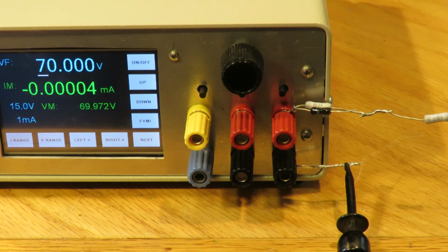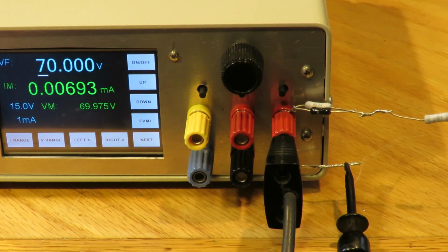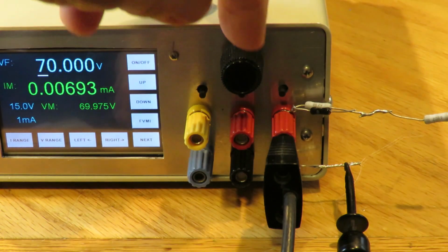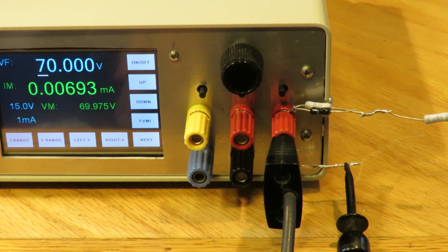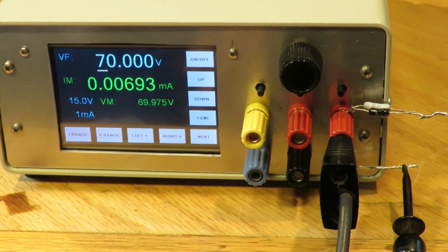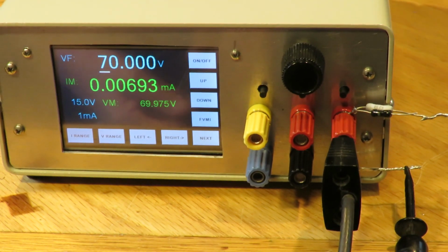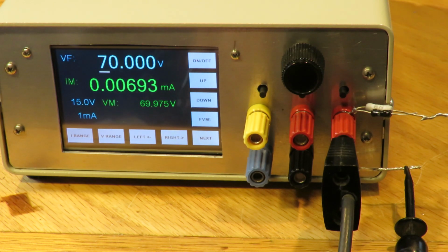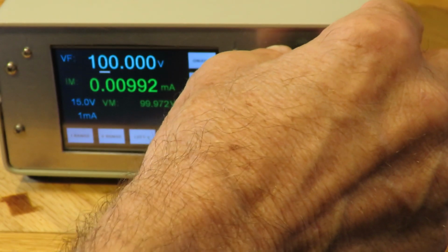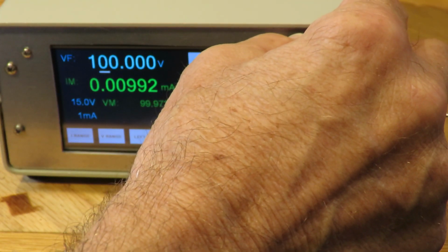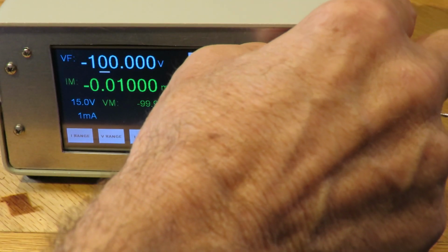And let me plug in my voltmeter. And you notice that there's a current reading now. When it first happened, I thought, oh, there's an error I'm going to have to fix, until I realized that current reading is because of the 10 megohm input resistance of the benchtop meter causing a current to flow at different voltages. So at 70 volts, you can see I'm drawing, at 100 volts I'm drawing 9.9 microamps. And at minus 100 volts, it's roughly 10 microamps.